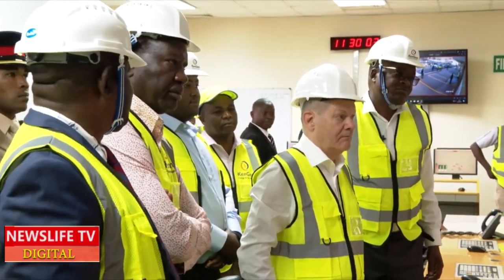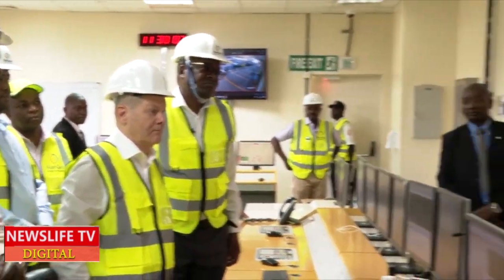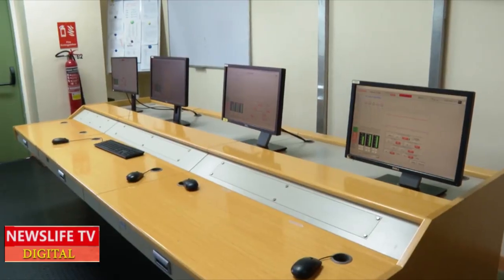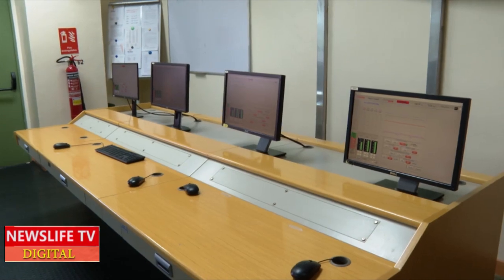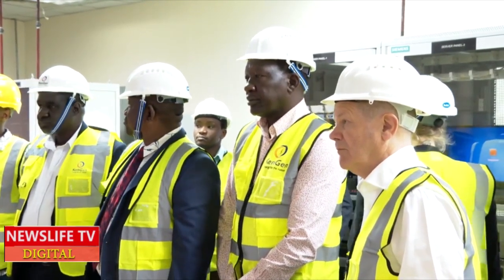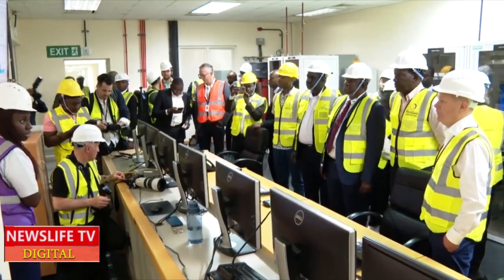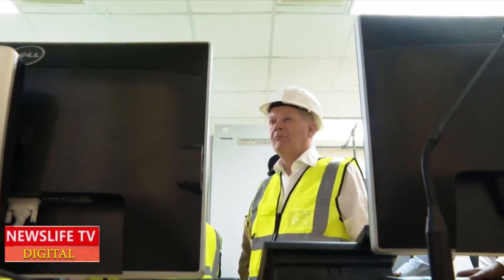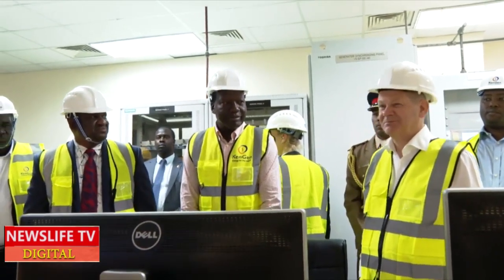And the saturated steam. So at the steam field, you normally do the separation of the brine from the saturated steam. So the brine now is rejected back to the ground. Once this is done, the condensate is formed and there are non-condensable gases. The non-condensable gases occupy space within the condenser, so we have to extract them, using either the ejector system or the vacuum pumps. So once this gas is extracted, that's an overview of how we generate electricity. Thank you.